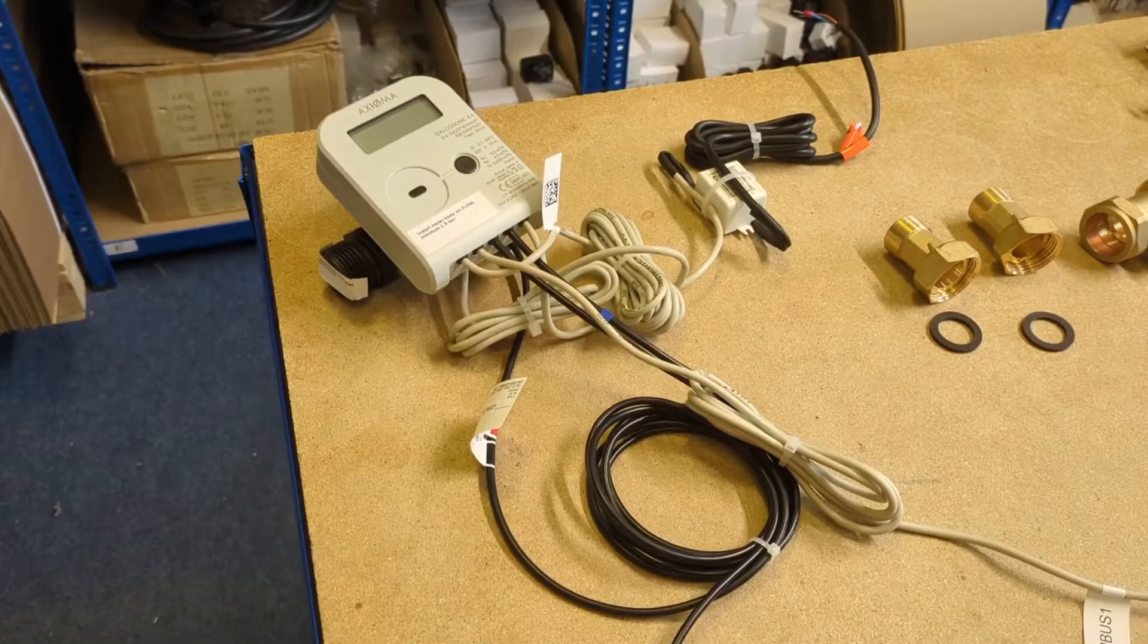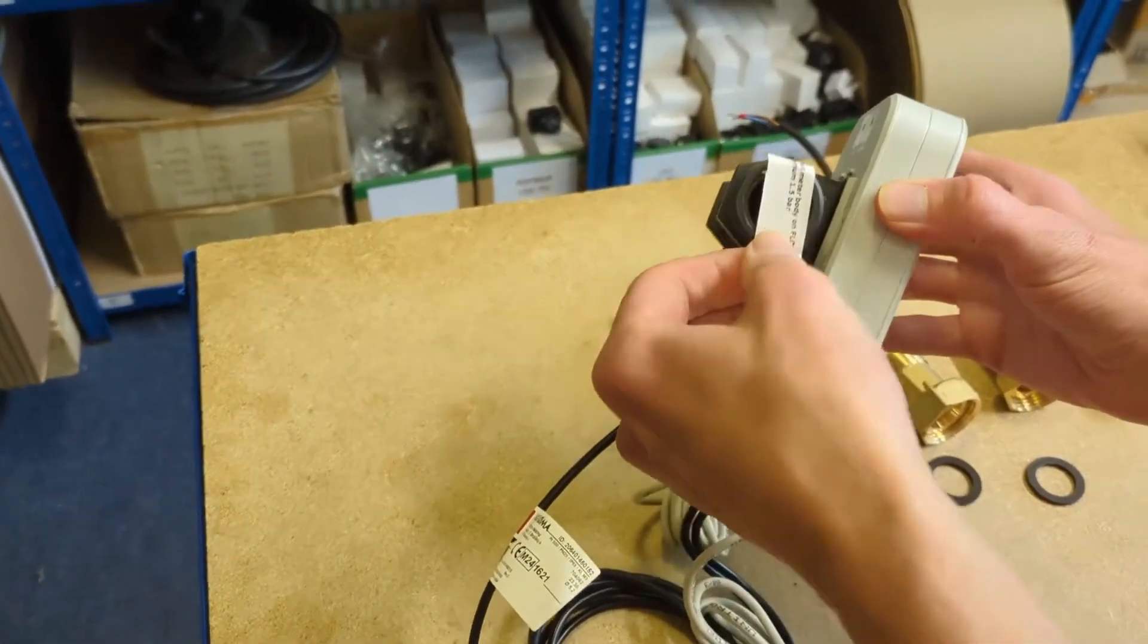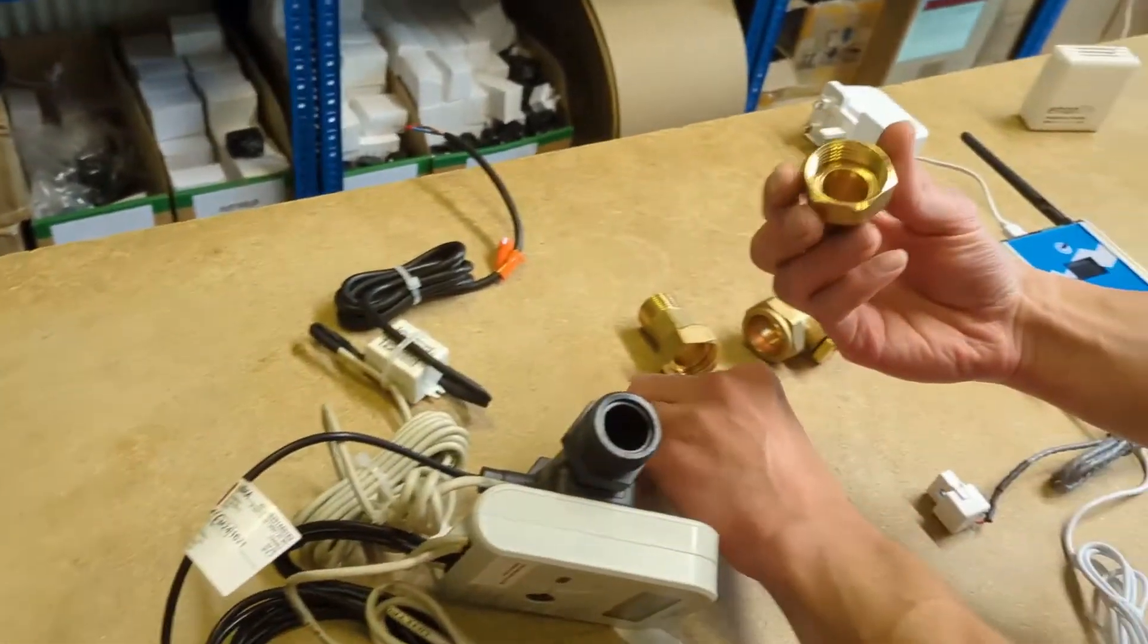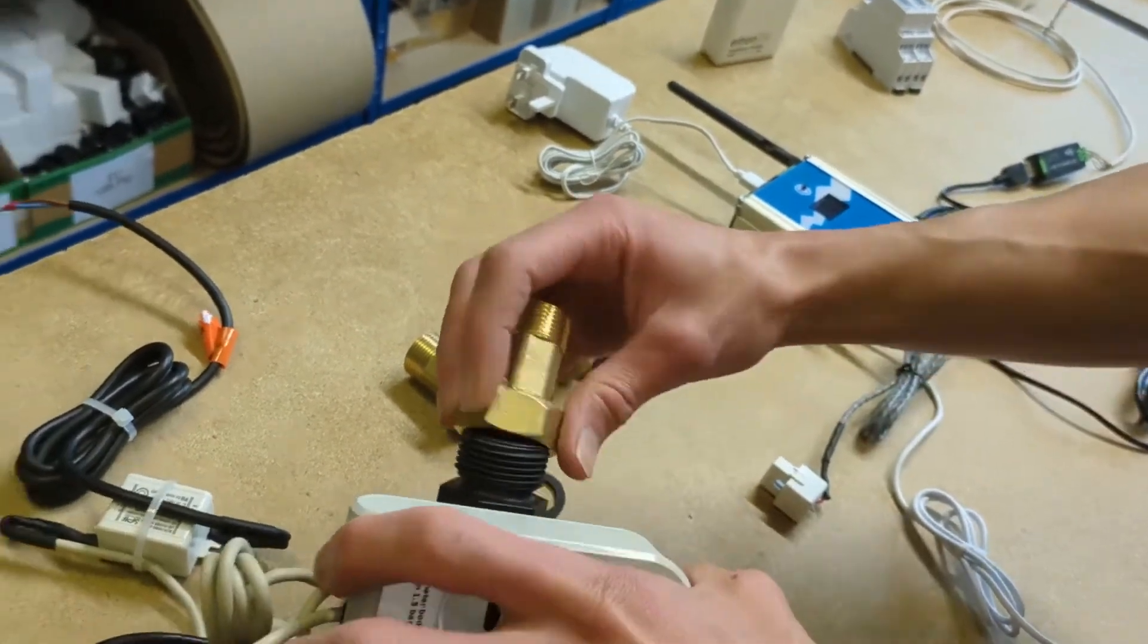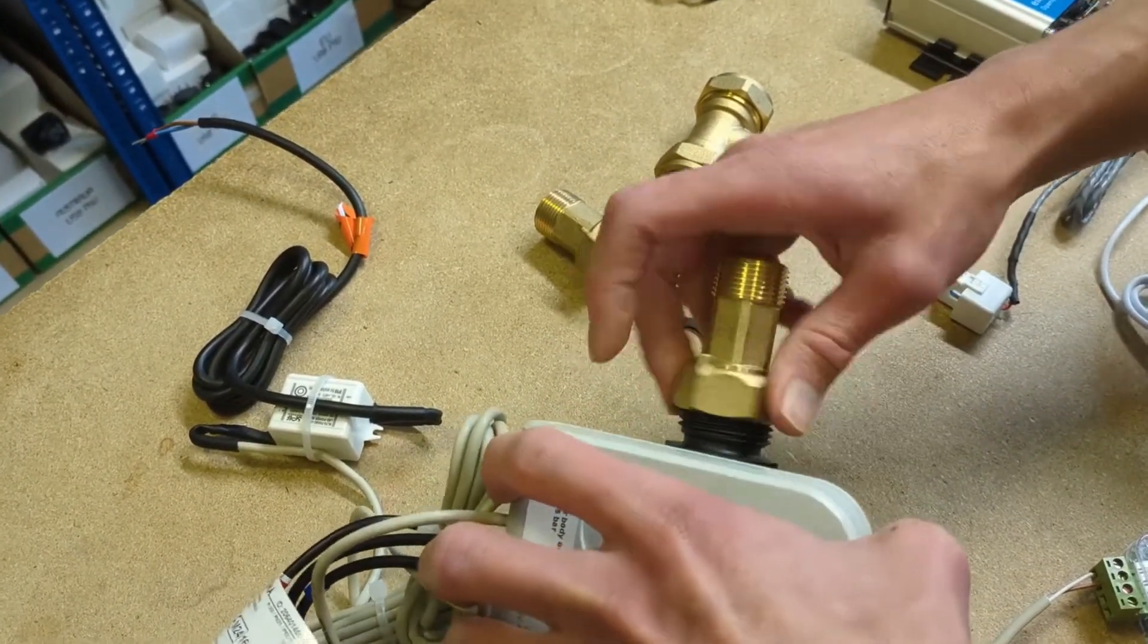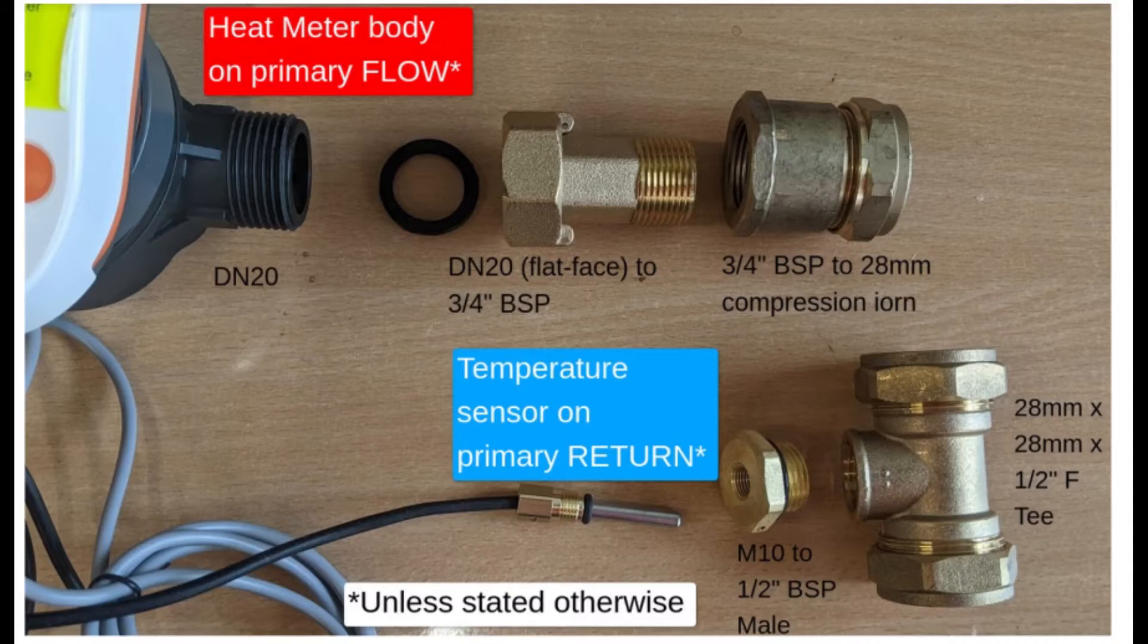This is the smallest heat meter we do. It has one inch parallel threads and is supplied with three quarter inch water meter unions. These are flat face unions with a rubber washer. You don't need to use these supplied water meter unions, but whatever fitting you do use needs to have a flat face. If you try and go on to these parallel threads with a BSP female iron, you'll have trouble sealing it up.